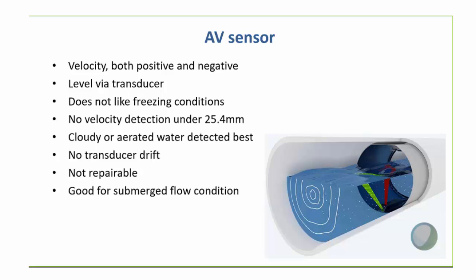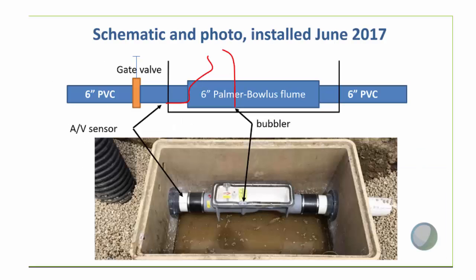The transducer, the level part of this, we don't see any drift at all. We're actually measuring in our work here in Ohio. We're using 2 different measurements, and we do not see any drift in that transducer. The unfortunate thing is these are not repairable. They are a sealed system. They do have to be sent back to the manufacturer for repair if something does go awry. They are very good for submerged flow conditions, which as we get into the second talk here, we'll be able to see that that's how we are using them.